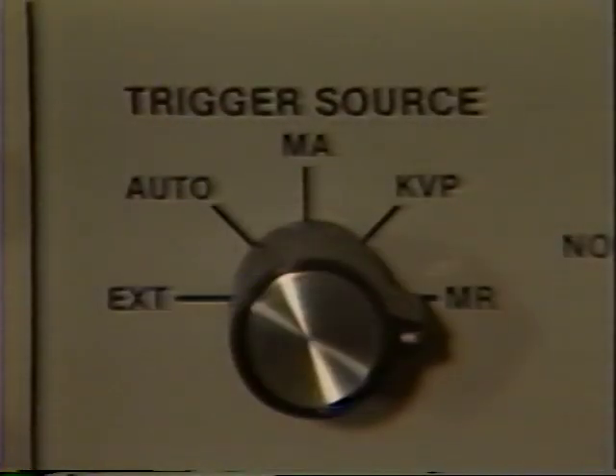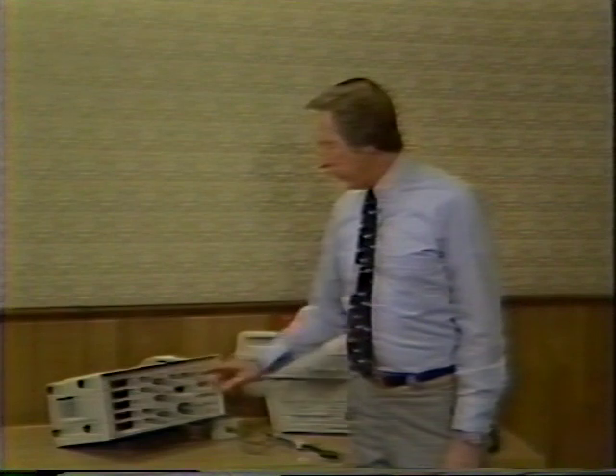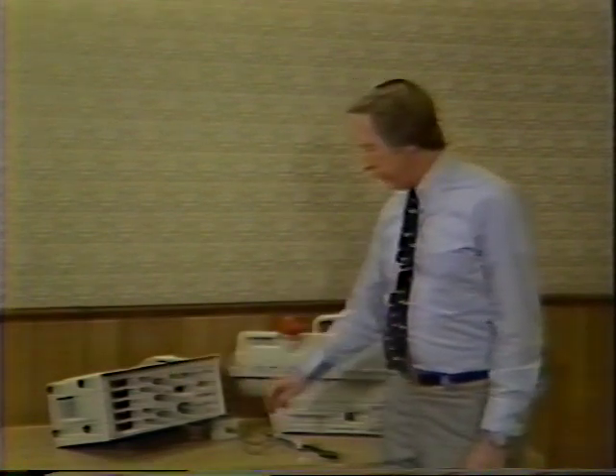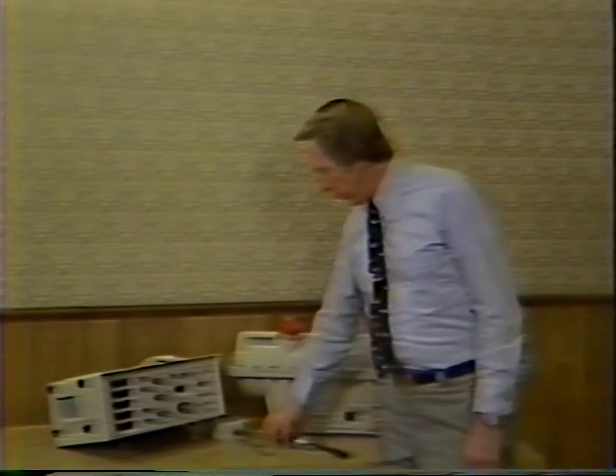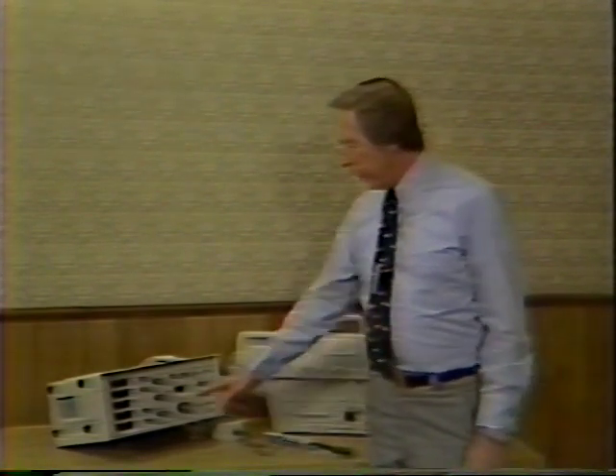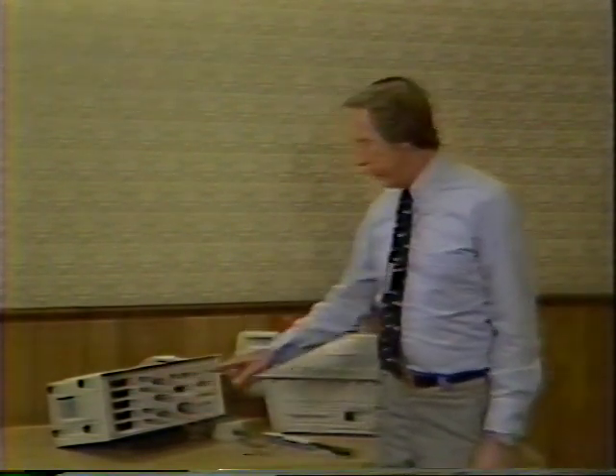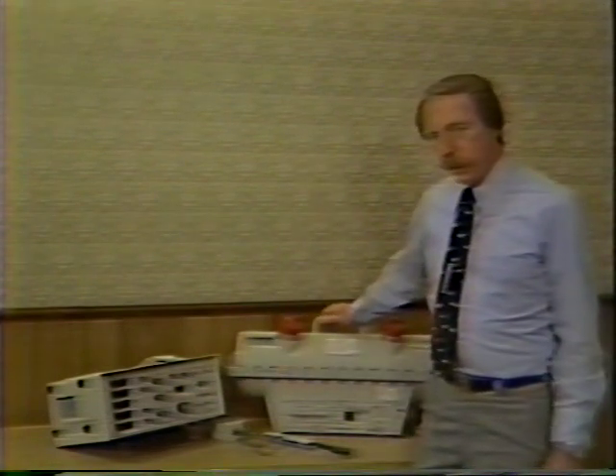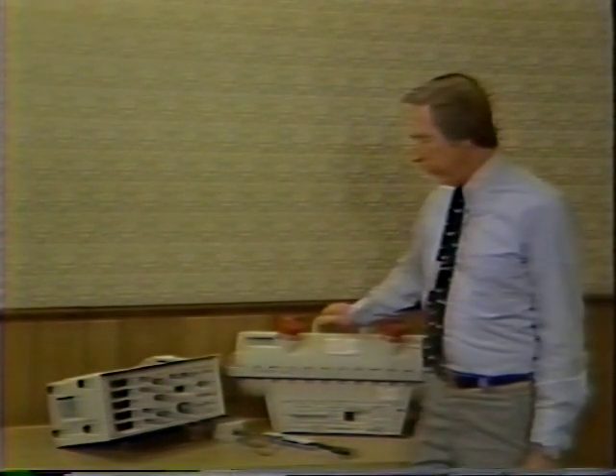The other position of the switch is mR. In this case, we plug this unit into the wall socket, put the radiation probe into the X-ray beam, take our shot, and we will then read mR and time. It is not necessary to have the high voltage unit in the circuit during that particular mode.